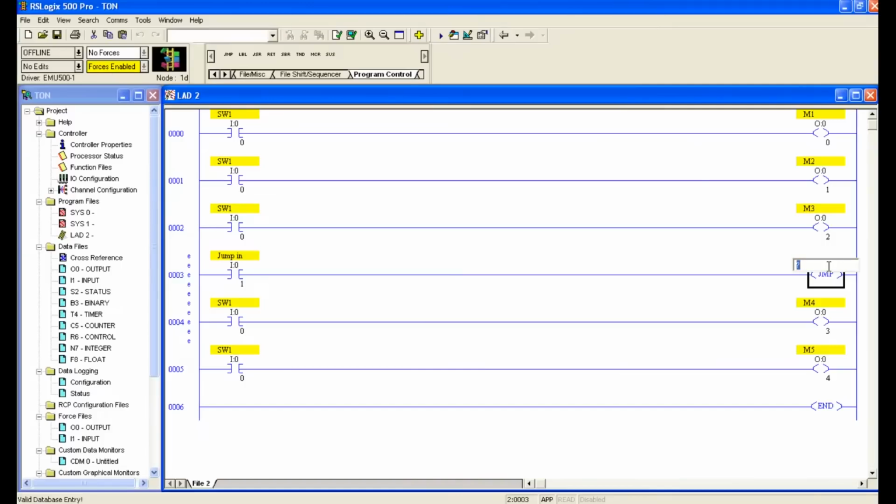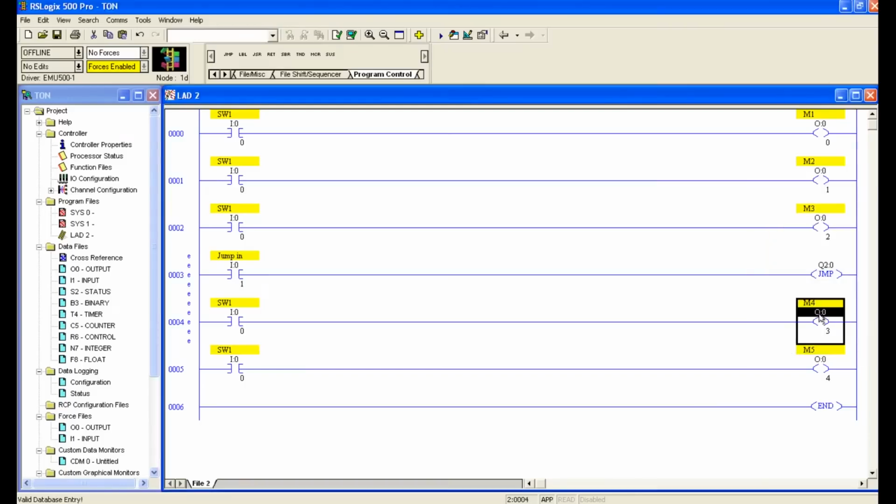In Allen Bradley, you need to give Q2 colon 0. You can start with 0. Even in the same program, if you are using some other jump, you can go for Q2 colon 1, Q2 colon 2, like that. It has a limit, depending upon the processor. Fine. So you have introduced a jump before the rung. You need to tell up to which one it skips. Here it is starting, then where is the end limit? That one also you need to tell.